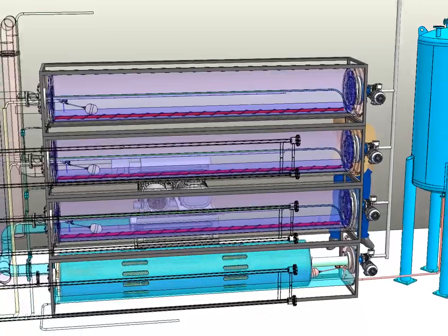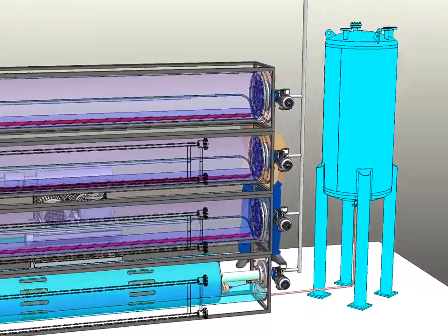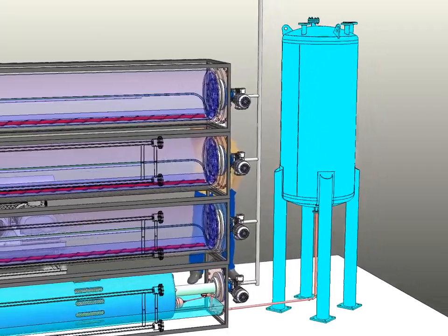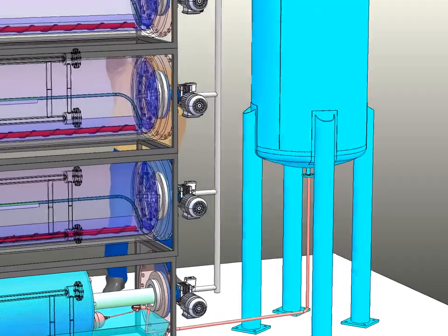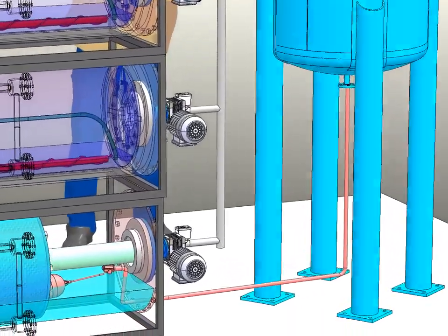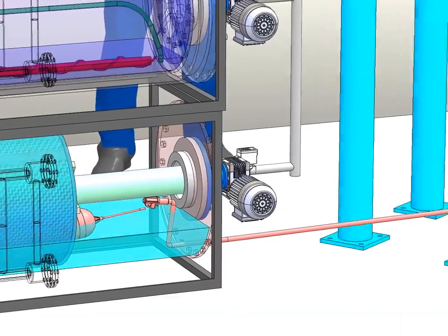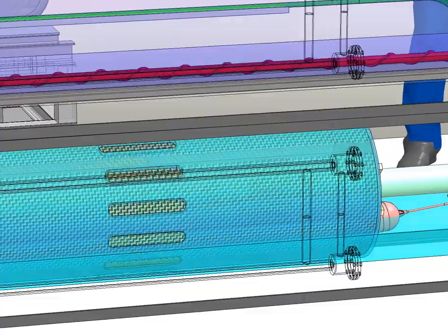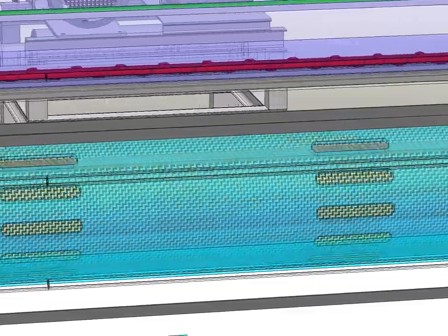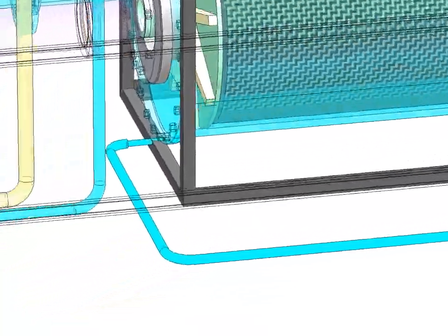The nozzle device is a rotating annular layer of nozzles located between 2 perforated shells. Polluted steam entering the central part passes through a rotating layer of nozzles and is cleaned from aerosols. The nozzles polluted with aerosols during the rotation of the annular layer are periodically washed by the circulating reflux and are cleaned of contaminants.